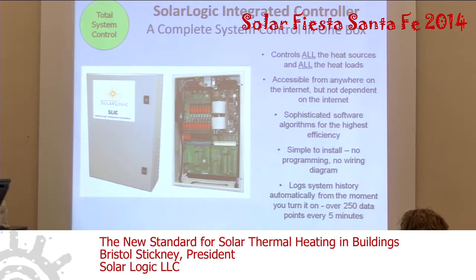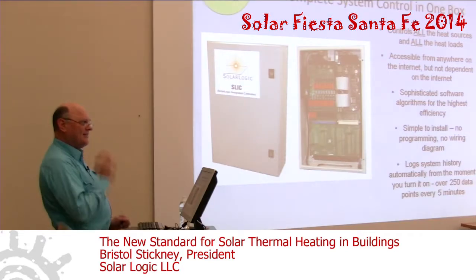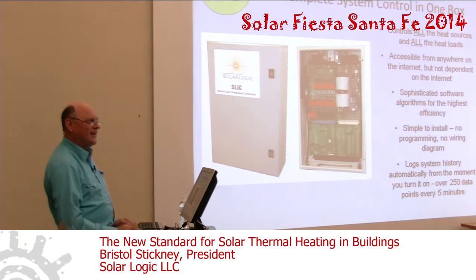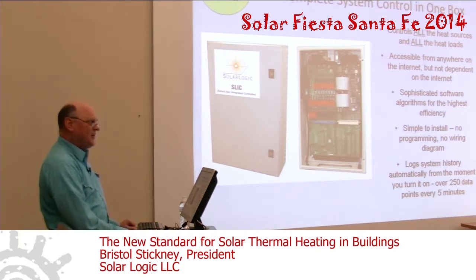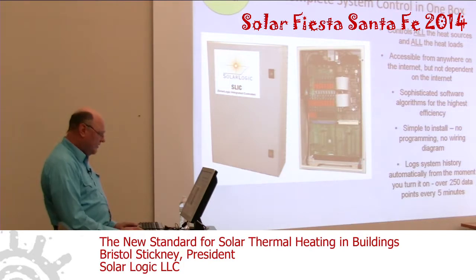And then down here at the bottom, that's where all the wires come in. So the room thermostats get wired here. All the little temperature sensors that make decisions get wired here at the bottom. All the zone valves, if you have zone valves feeding heat to different zones in the house, get wired here. And all the pumps get wired right here. So everything to do with heating in the house, every pump, every valve, every sensor is wired to this box. And then the box, through its computer, reads what's going on and makes intelligent decisions to guarantee that your solar heating system will provide the solar heat it's supposed to provide at the highest possible efficiency.